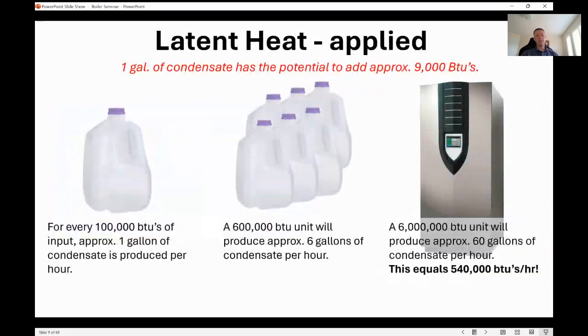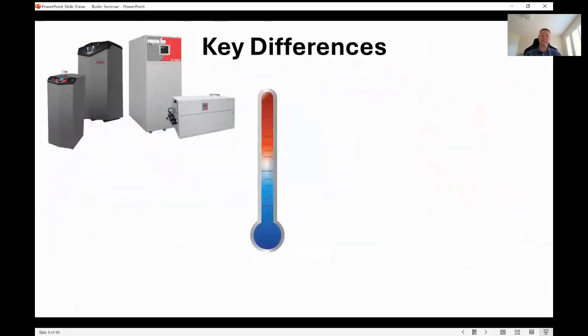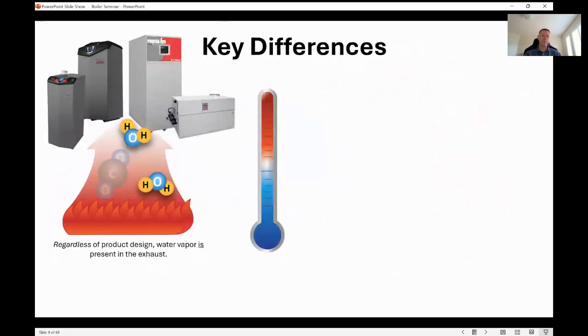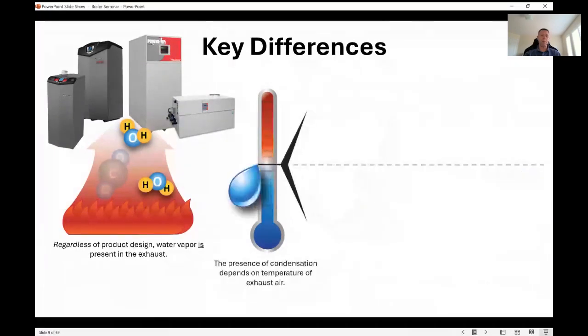Put this in perspective for you guys. If you have a 100,000 BTU boiler, for every 100,000 BTUs, you're going to get 1 gallon of condensate produced roughly every hour. So if you have a 600,000 BTU per hour boiler, you're going to get 6 gallons of condensate every hour. And of course, with a 6 million, you're going to get up to 60 gallons of condensate produced every hour. So this 6 million BTU boiler will produce roughly an extra 540,000 BTU per hour, every hour, just from changing state in the flue products there and turning that gaseous water vapor into liquid. So the key difference between the two is that one of them is able to operate below that dew point.